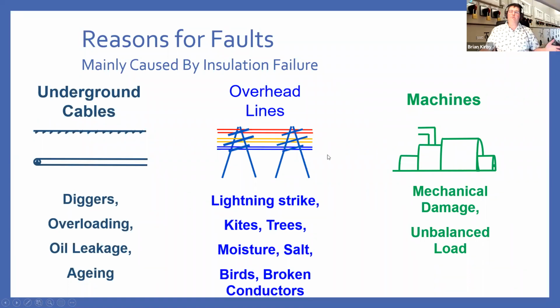Overhead lines, as we've mentioned previously, are exposed to the elements. So lightning strikes are common. Anything that's in the air nearby in their electrical or corona area, so kites, trees. If you're near the coast or near a waterfall or something, you may have lots of moisture or salt in the air. Large groups of birds can cause problems if they all decide to roost on the cable simultaneously and all take off simultaneously, causing oscillations which can cause the clearances between conductors to be exceeded, or broken conductors. Say, for example, you get ice buildup, which causes the conductor to come down.